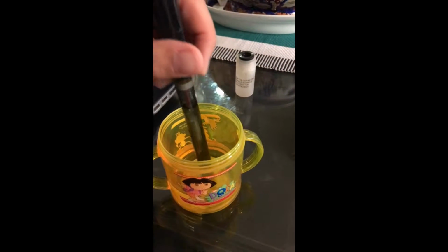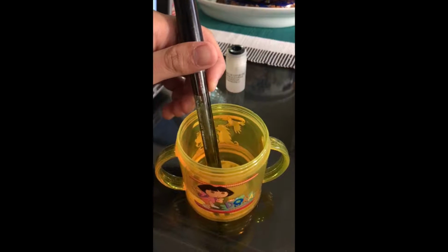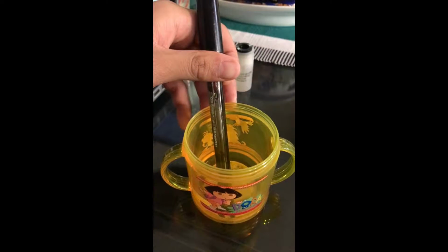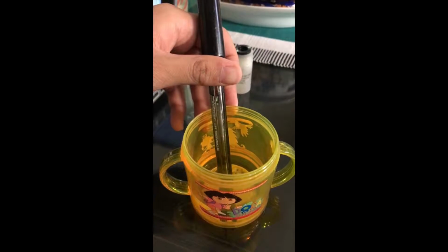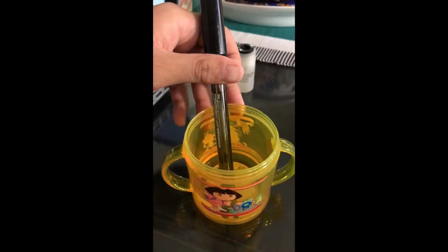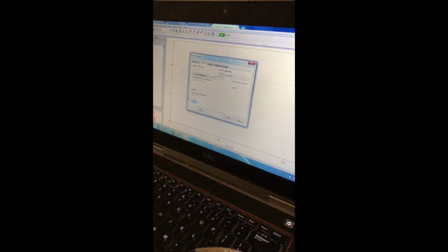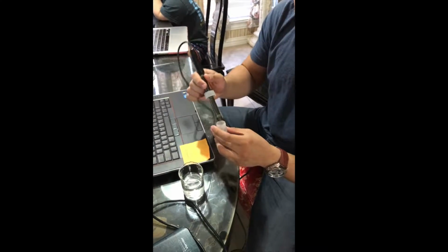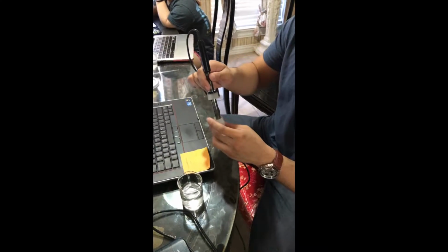So after we click that, we click Calibrate, and we let our pH probe sit within the container so that the pH will reach a stopping point, so that the pH reader can precisely read it. After it's sat there for about 15 to 20 seconds, we go over there and manually enter in a pH of 7 for our distilled water. Afterwards, we keep our point and we click Done, and we will see that the pH reading at the bottom left-hand corner will say 7. So now we have calibrated.